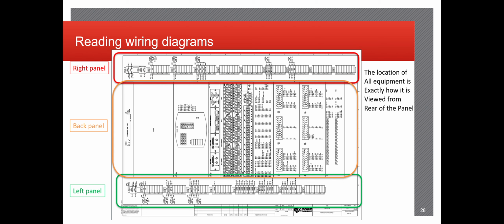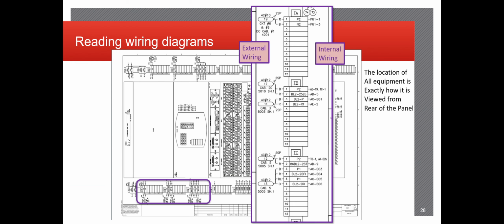So when we're looking at a wiring diagram, always be aware that you're looking at it based on the back of the panel. So if you're looking at the back of the panel, the terminal blocks to the right will be on the right side, for example. When you're looking at the terminal blocks, depending on which side you're on, this is very important, it will determine whether you have external or internal wiring. For example, where we have circled here, it's going to be on the left side of the panel, meaning that the outermost parts will always be the external wiring that's coming in or leaving, going to another cabinet, and anything on the insides of those terminal blocks is just in this panel, for example.